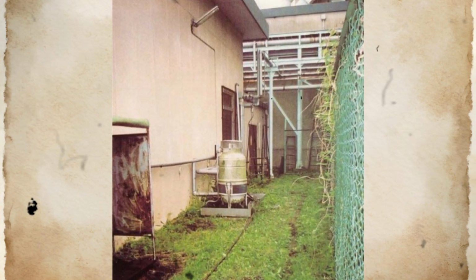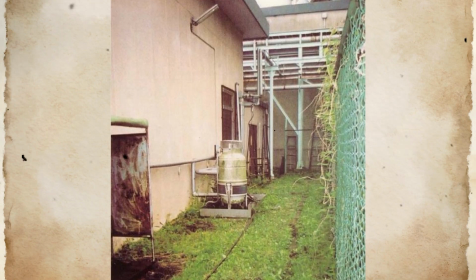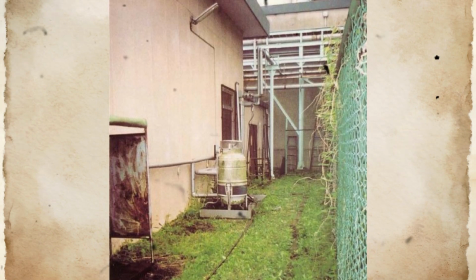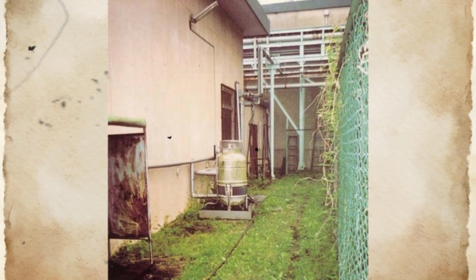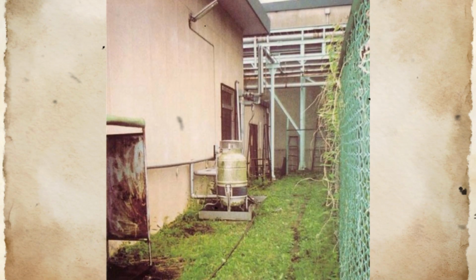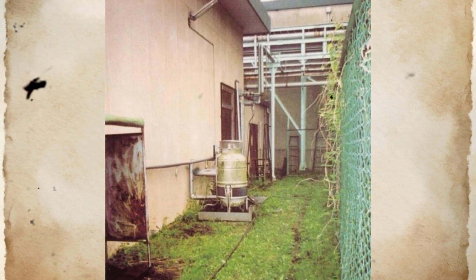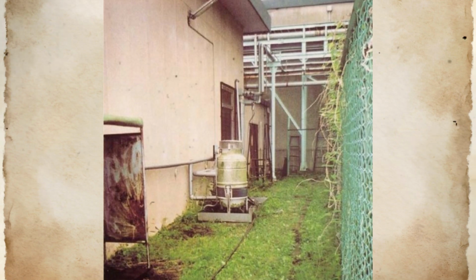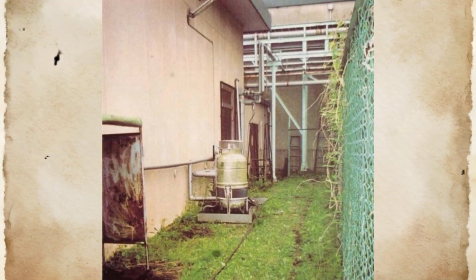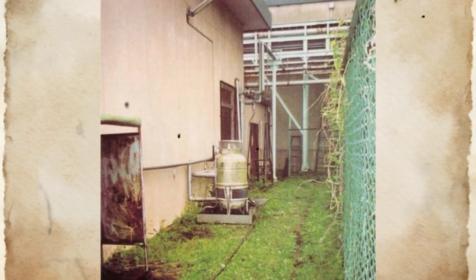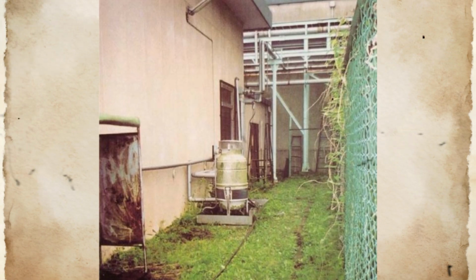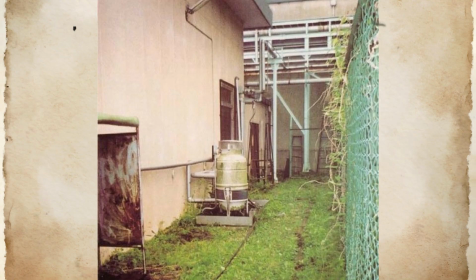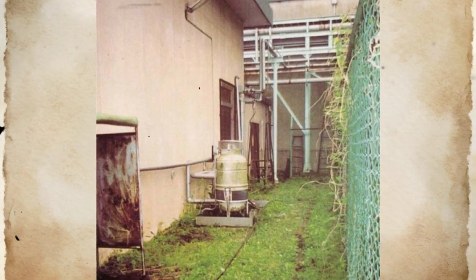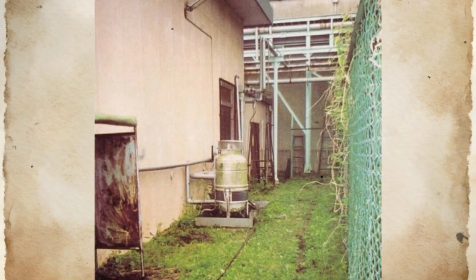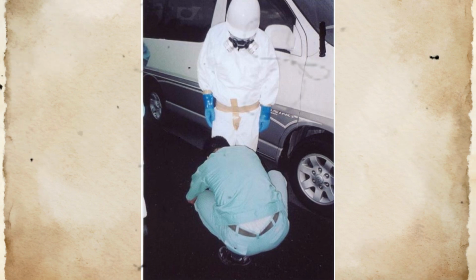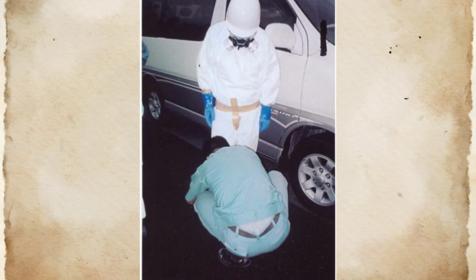The wave height, measuring 14 to 15 meters above standard sea level, overwhelmed defensive barriers sized for the design basis threat. Seawater flooded the turbine building basement where the emergency diesel generators were located, not because the generators themselves were poorly designed, but because the comprehensive threat assessment had underestimated the correlation between seismic and flooding hazards. The emergency power systems failed not individually but collectively, a common cause failure that the multiple, independent design philosophy was intended to prevent. Unit 1's emergency diesel generators stopped at 1537, Units 2 and 3 at 1541, and Unit 4 at 1538. The timing was nearly simultaneous because the failure mechanism, flooding of electrical equipment by tsunami water, affected all units equally.